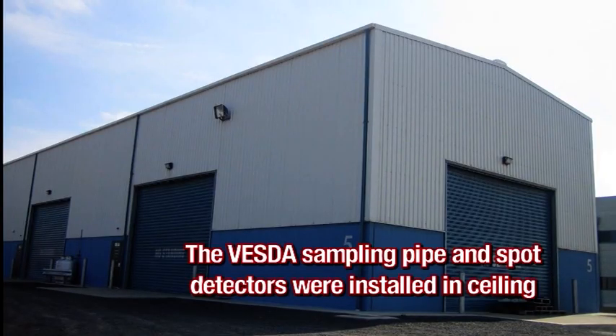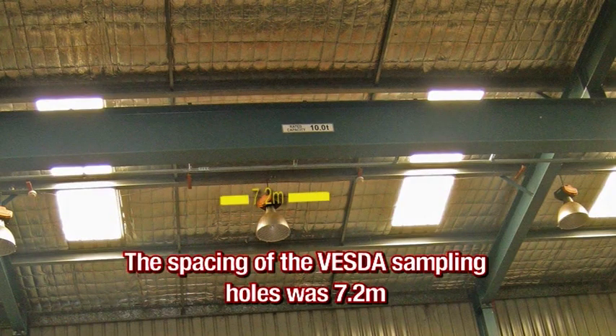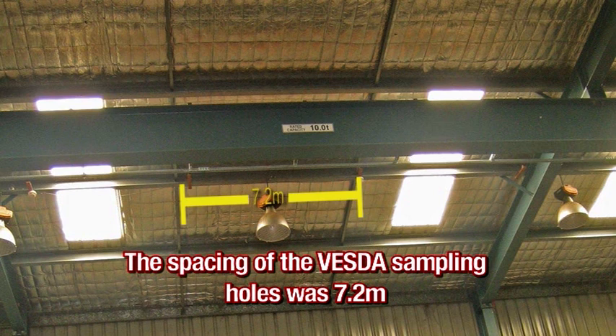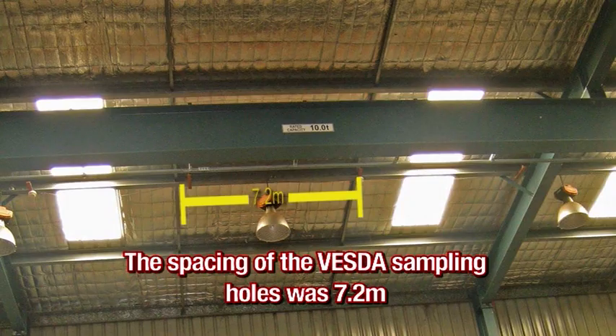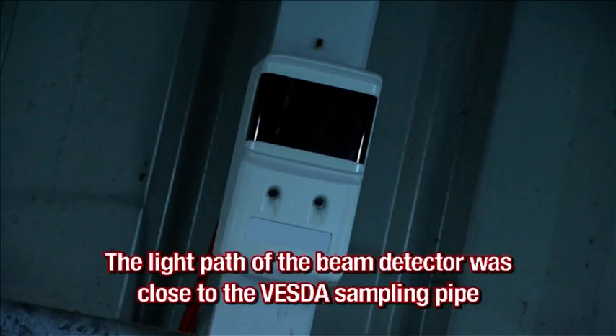Some key points to note about the tests are that the VESDA sampling pipe and spot detectors were installed at the warehouse ceiling. The spacing of the VESDA sampling holes was 7.2 meters and spot detectors were mounted next to each VESDA sampling hole. The light path of the beam detector was close to the VESDA sampling pipe.